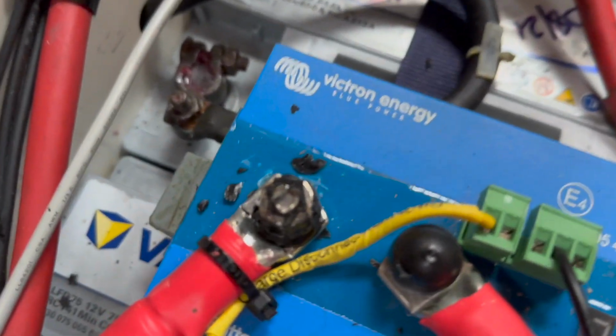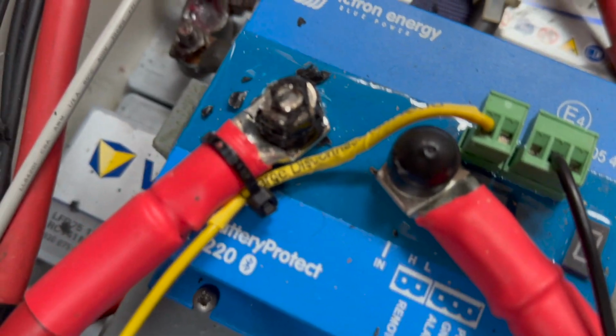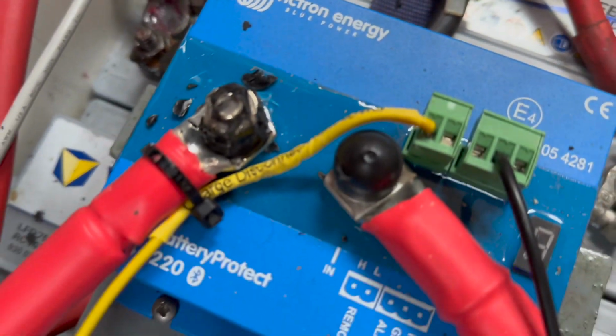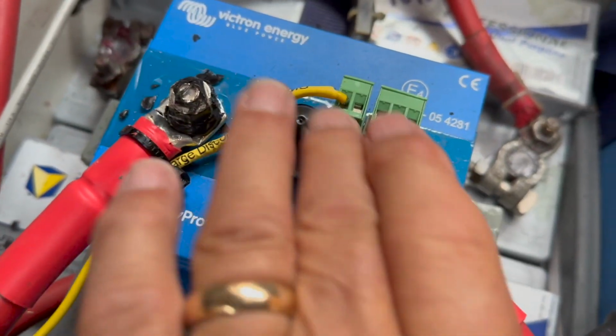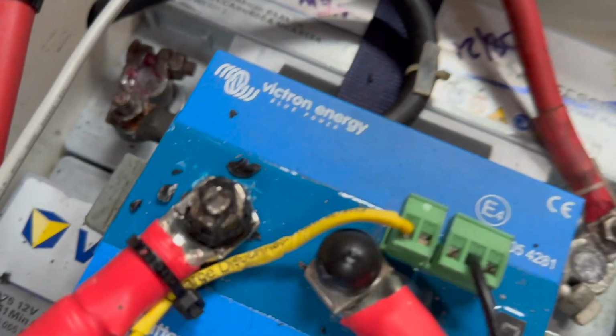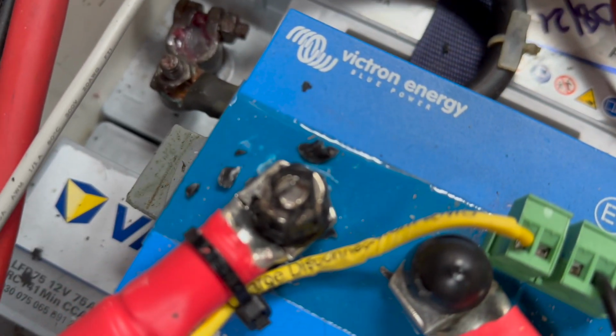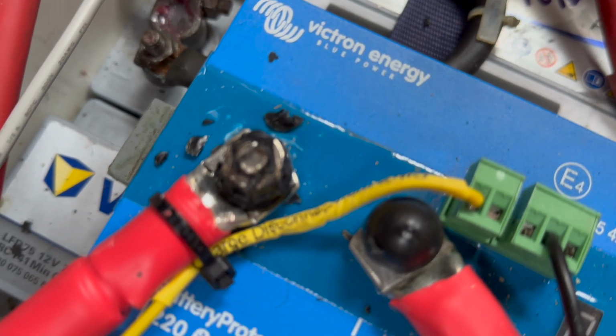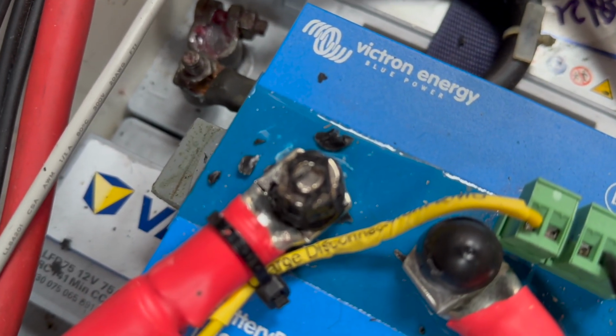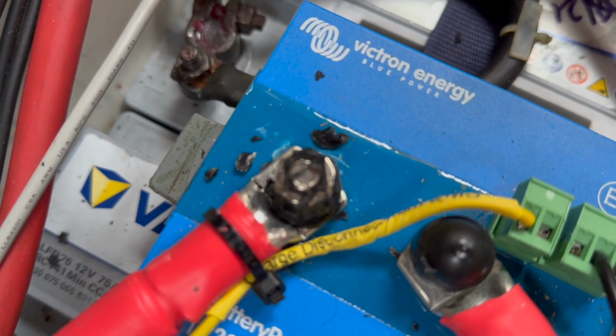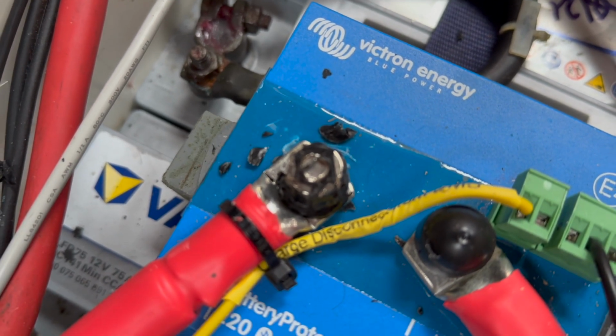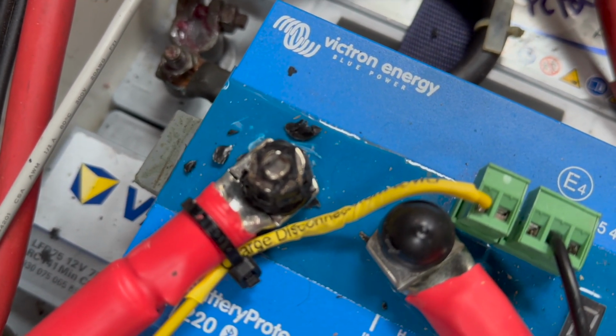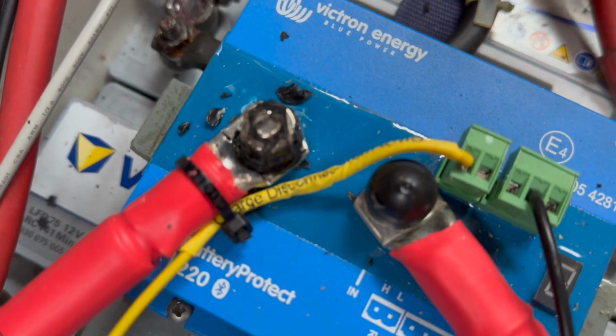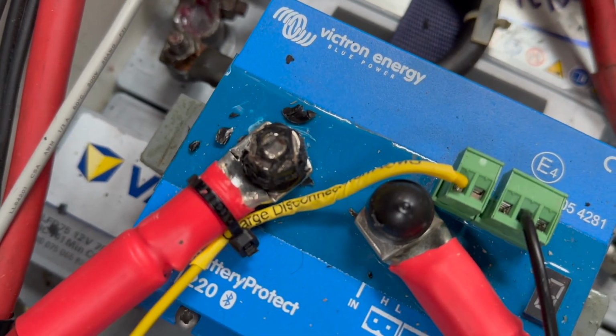So this thing was the fault that we found. I've cut it away since then, but it had one of these plastic caps on it, like this black plastic cap, just so that if anything fell in there it didn't immediately arc. This was warm, and it obviously cooled down since the incident, because it was probably about half an hour later when I got to this point. So that's what it was. I tightened it down and everything worked okay.